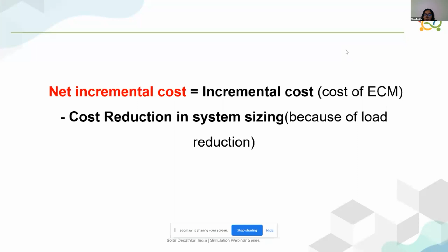So in order to account for energy savings in system sizing, we have a term called net incremental cost. Net incremental cost is nothing but the cost of the ECM, for example the cost of DGU and installation of DGU, minus the cost reduction in system sizing because of the load reduction. So say if the DGU costs roughly around 2,000 rupees per square feet, and there is a significant percentage reduction, almost 25% reduction in HVAC system sizing, we account for that in this term called net incremental cost. So in this slide, you can see that I have shown two parameters here. The parameter in blue is the savings in cooling capacity, and the parameter in red is incremental cost.